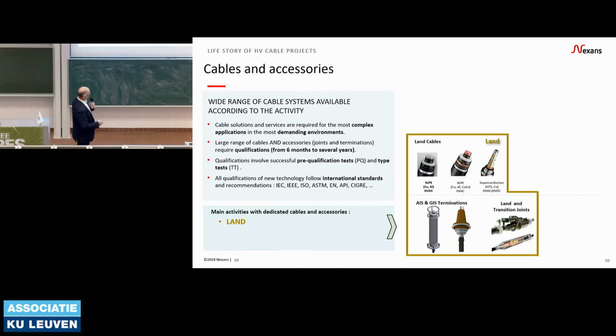And sometimes it requires special accessories, like you see here, for example. This one is the interconnection between a crosslinked polyethylene cable, a synthetic cable, and a paper insulated cable. So sometimes you have to link two technologies together, and the accessory has to be built accordingly.